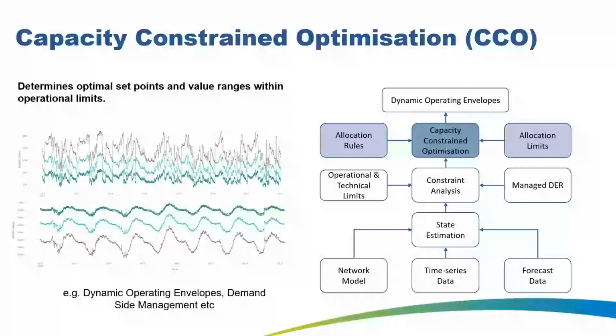That doesn't necessarily get the most renewable generation pumping back into the system. If you want to do that, then that's a different optimization approach, and what you might end up with is customers on low voltage networks closer to their transformer contributing more power exporting into the network, but only if customers at the end of the feeder throttle back their export, since they're more likely to have export contributing to voltage rise. That means we're hitting a voltage limit, which means we can't get any more export.